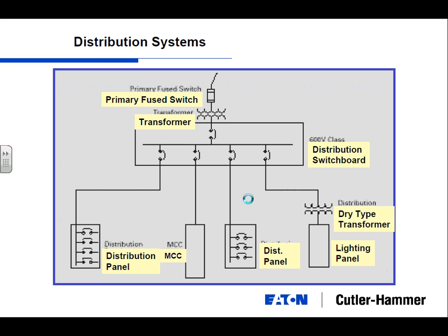Okay, so drilling down inside the building, for the sake of this, this will be the guideline of the power distribution system. Coming in, you'll have a transformer here. You'll have some kind of fusible switch, and this transformer here then will step it down to your user voltage, and you can put this anywhere. This could be owner supplied equipment inside the building or utility supplied equipment outside the building.